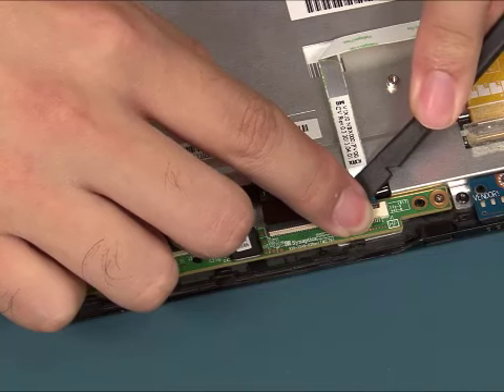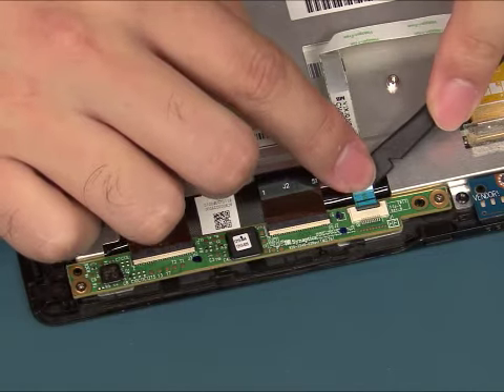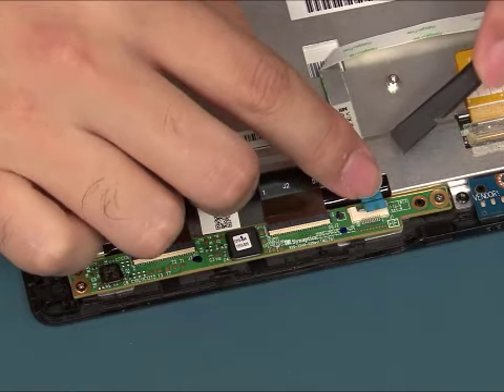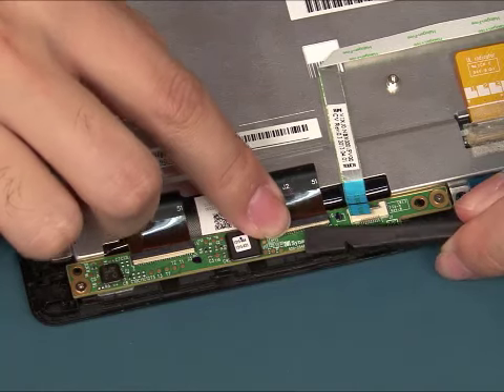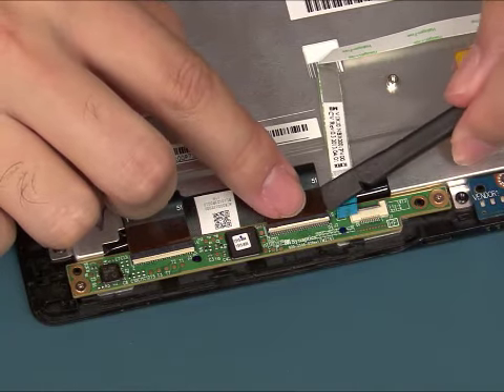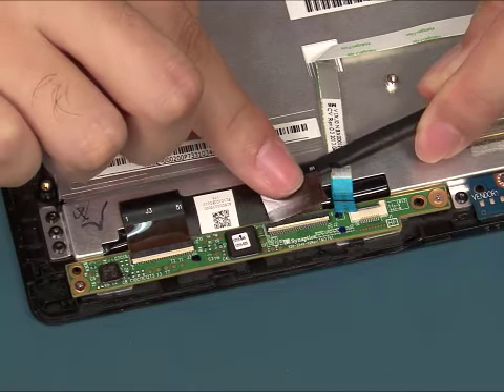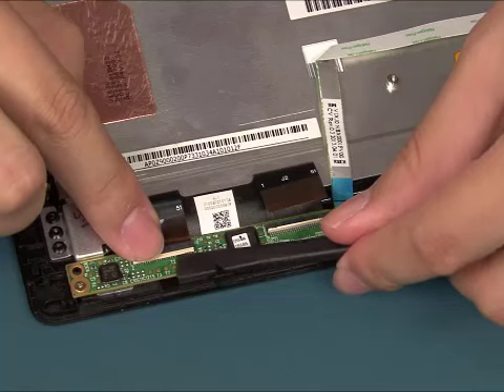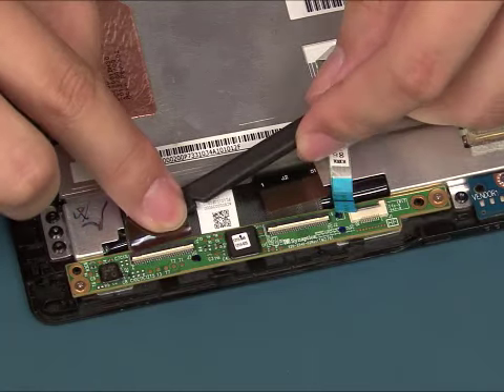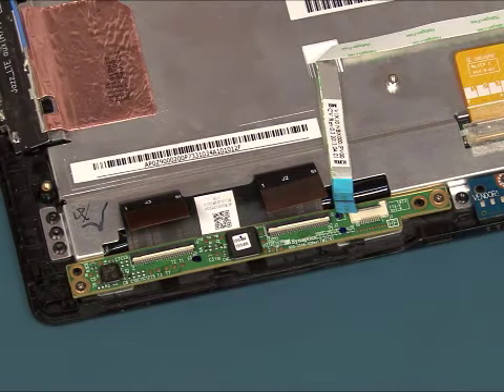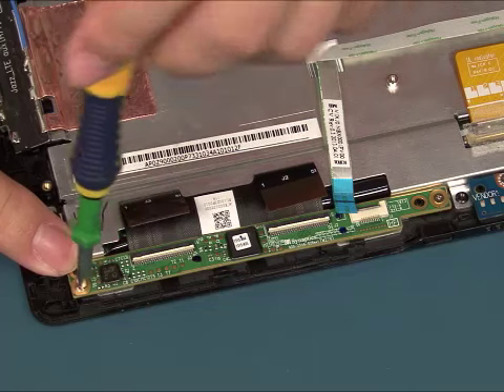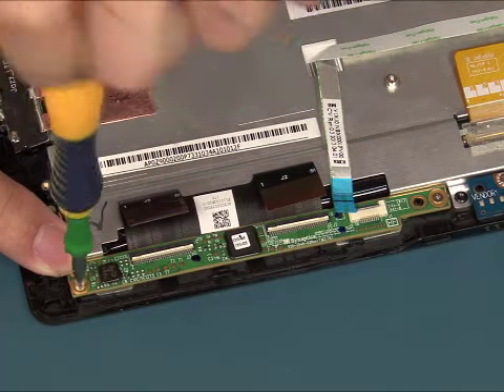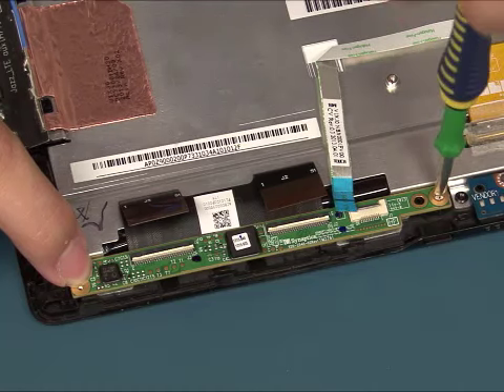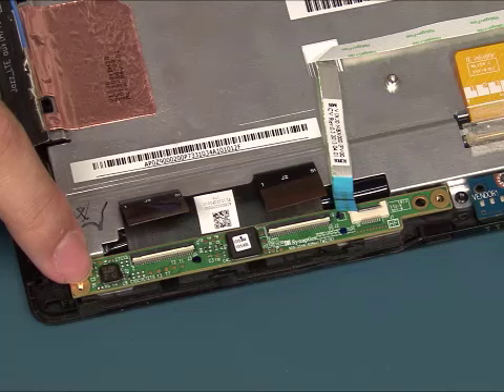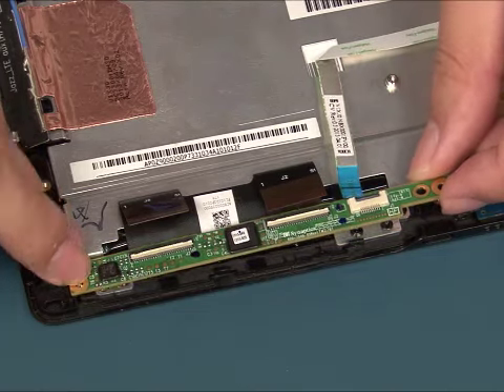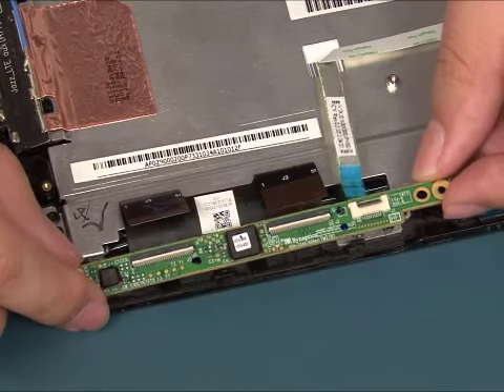Release the ZIF connector. Disconnect the signal cable. Disconnect the ribbon cables from the system board. Remove the 2 screws that secure the touch control board to the frame. Lift up to remove the touch control board.